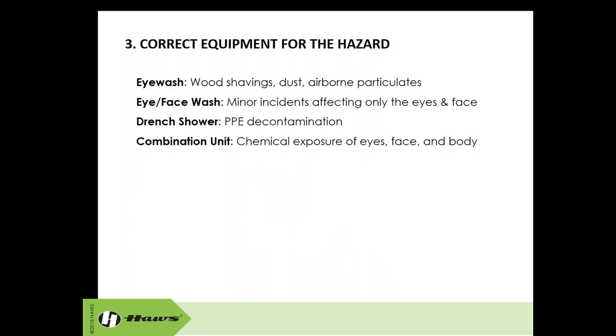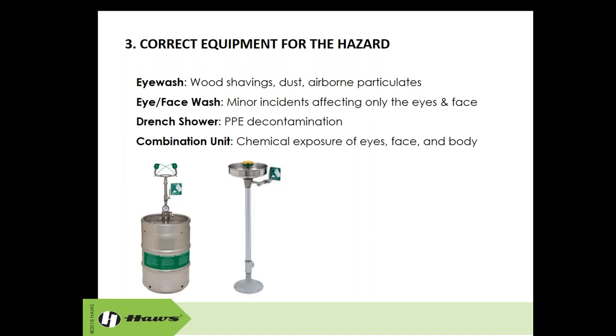Now, the correct equipment for the hazard is most important when you're deciding what type of equipment is going to go in place. You need to keep these in mind, okay? An eyewash is for airborne particulates, wood shavings, dust, anything that can fly up and is not going to harm your skin, okay? An eye face wash is for minor incidents affecting only the eyes and face. This typically means a heavily gowned PPE type situation, or with a low enough pH that it's only going to affect your face and your eyes.